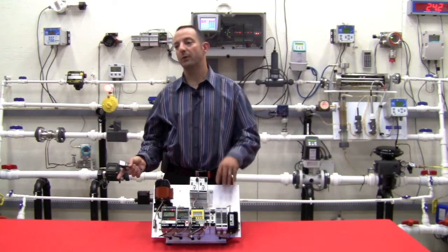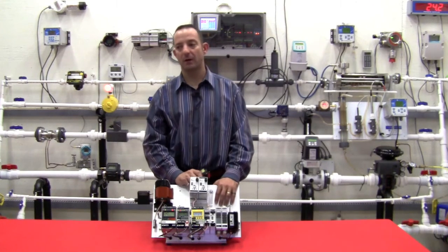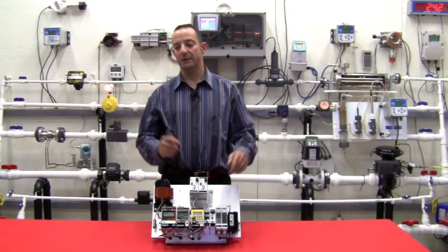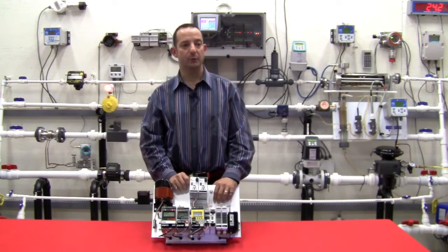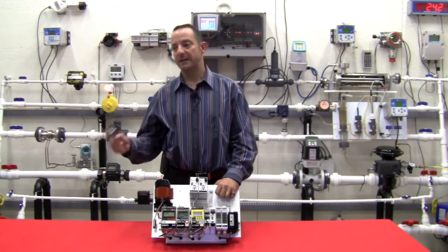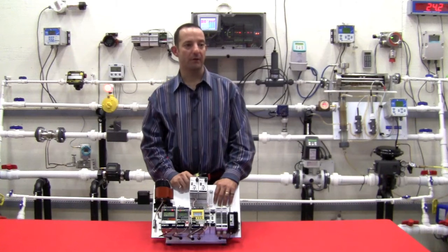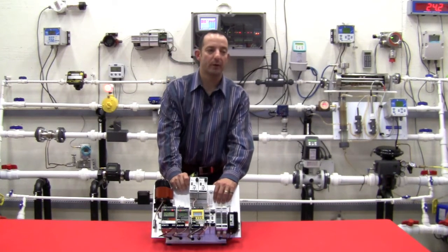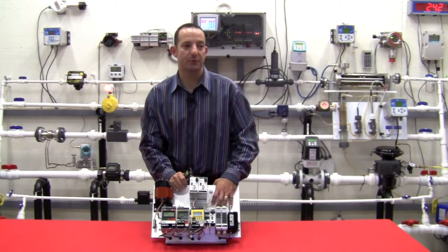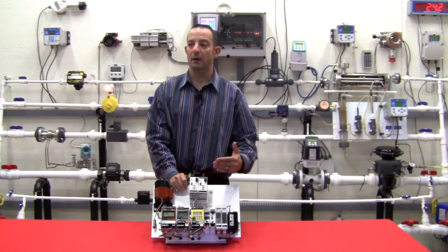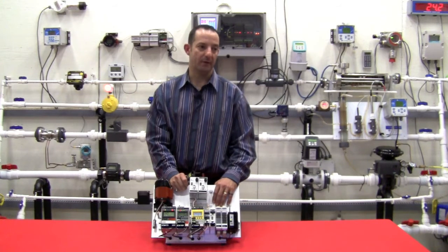Where you have more than one signal ground in an analog current loop, the isolator breaks the loop in the middle and sets up 2 independent loops, each with equal signal values, but each of those loops has only one ground. Again, if you don't completely understand the concept of a ground loop and why it affects signals, please refer to our isolators and ground loops brochure in the literature file.